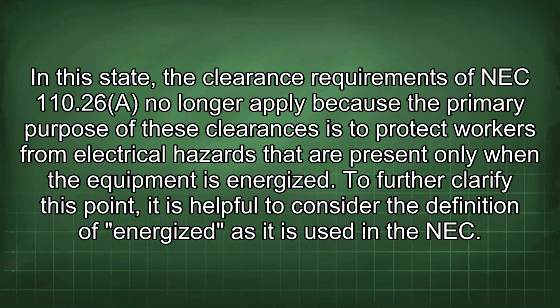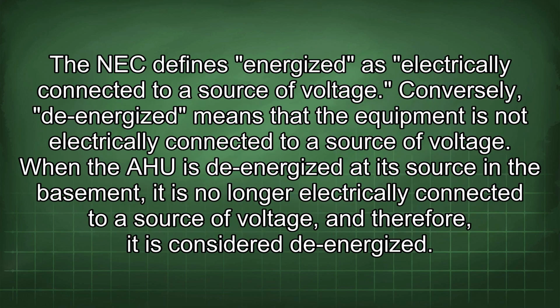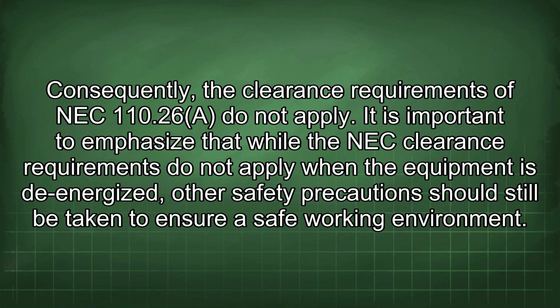To further clarify this point, it is helpful to consider the definition of energized as it is used in the NEC. The NEC defines energized as electrically connected to a source of voltage. Conversely, de-energized means that the equipment is not electrically connected to a source of voltage. When the AHU is de-energized at its source in the basement, it is no longer electrically connected to a source of voltage, and therefore, it is considered de-energized. Consequently, the clearance requirements of NEC 110.26 do not apply.